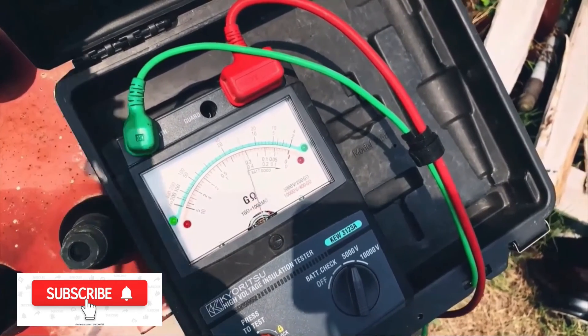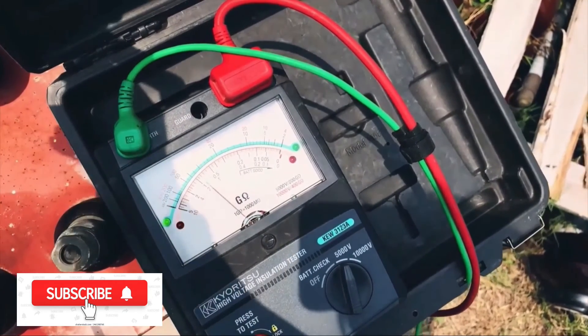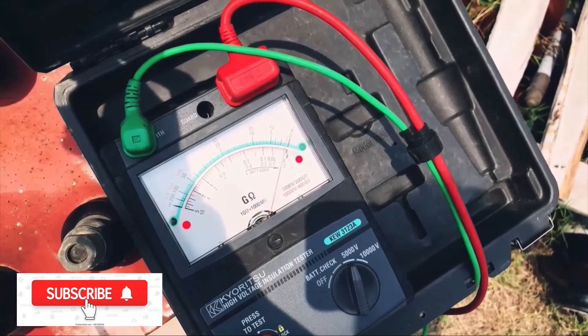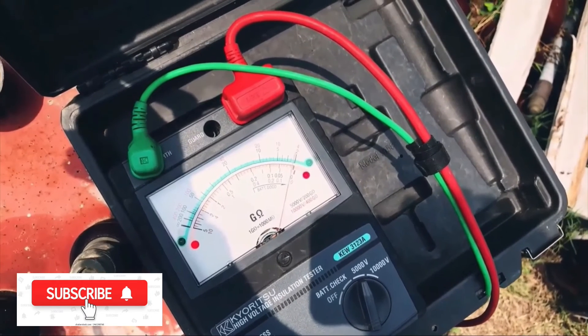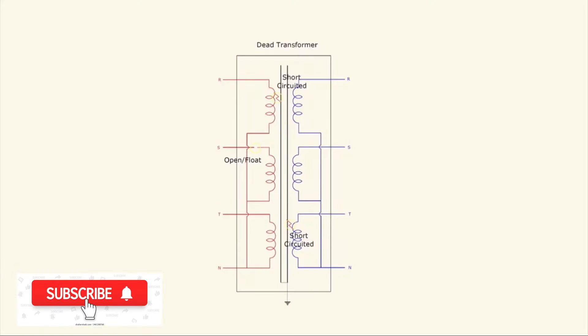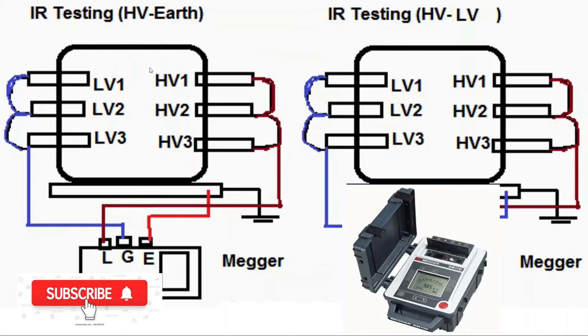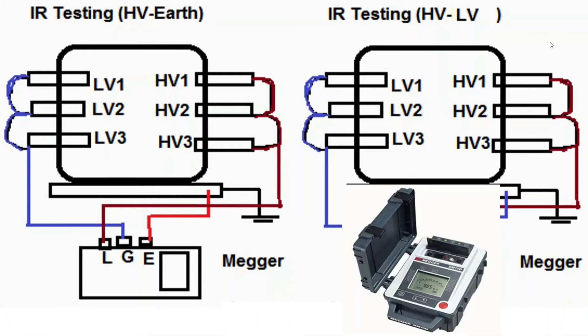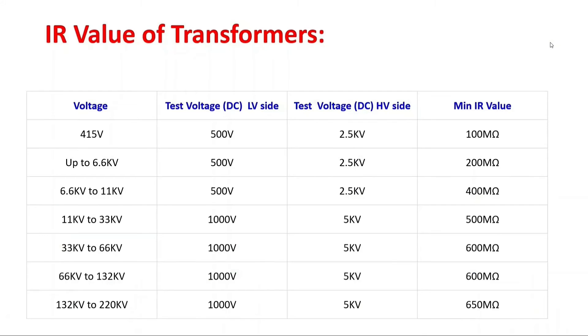IR values of transformers: as shown in the figure, test voltage on the 415 V side — DC LV side 500 V test voltage; DC HV side 2.5 kV. Minimum insulation resistance value: 100 megaohms.